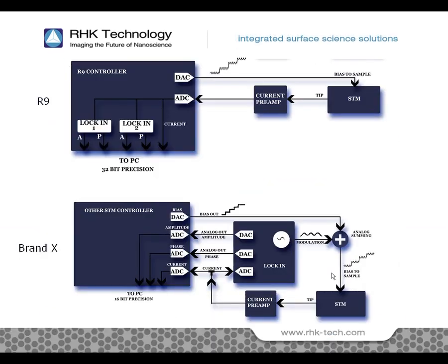One example of the advantage of the R9 approach can be seen in the configuration required to make DI/DV measurements. With the R9 having the lock-ins fully integrated, it can be seen that the analog signal from the preamp is only digitized once. From that point, the signal travels through the R9 as digital data. This digital data feeds the feedback loop in both lock-in amplifiers. All the signals, including the current, topography, and the lock-in signals, maintain their full 32-bit precision and are stored directly without ever having been converted back to analog signals.